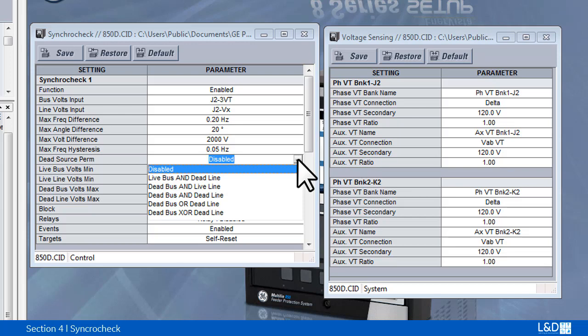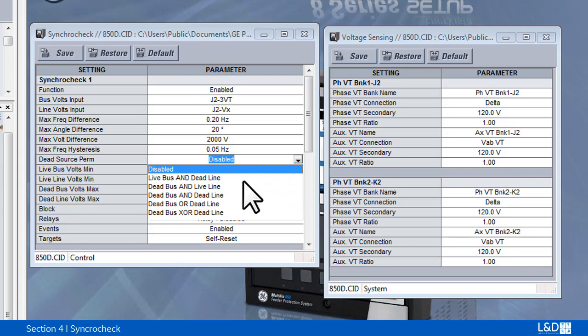Dead source permission disabled means the mode is disabled. Live bus and dead line. Dead bus and live line. Dead bus and dead line. Dead bus or dead line. Dead bus exclusive or dead line, which means one source is dead another one is live.